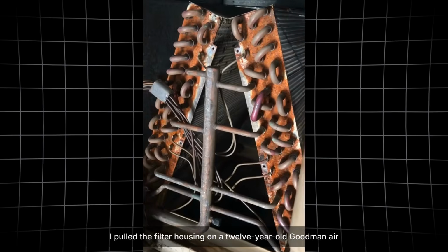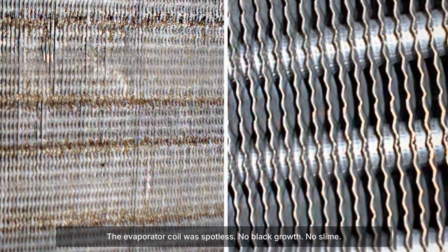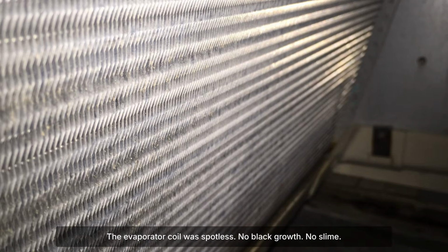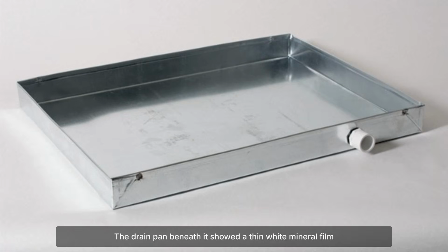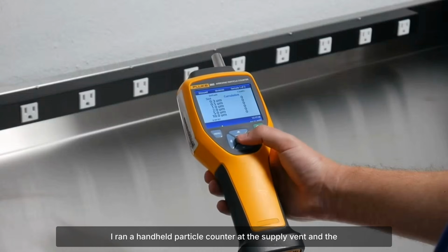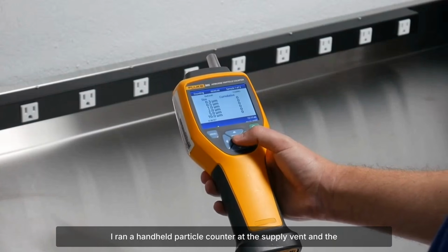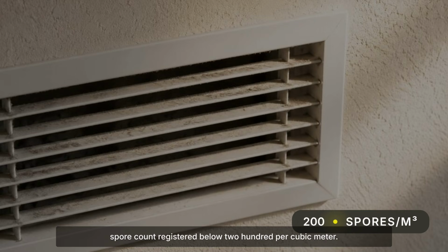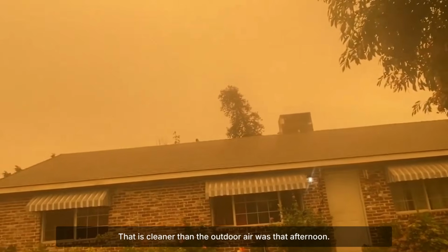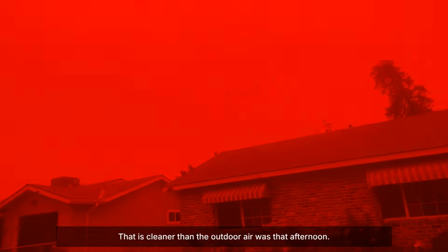I pulled the filter housing on a 12-year-old Goodman air handler in one of his duplexes. The evaporator coil was spotless, no black growth, no slime. The drain pan beneath it showed a thin white mineral film and nothing else. I ran a handheld particle counter at the supply vent, and the spore count registered below 200 per cubic meter. That is cleaner than the outdoor air was that afternoon.